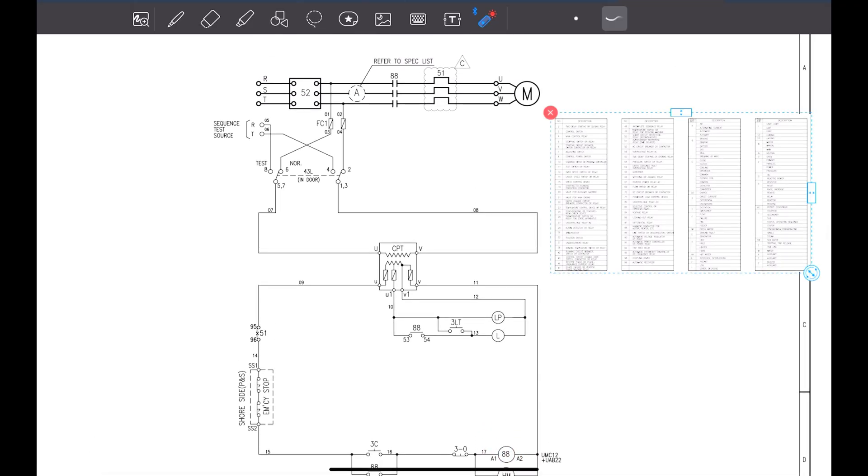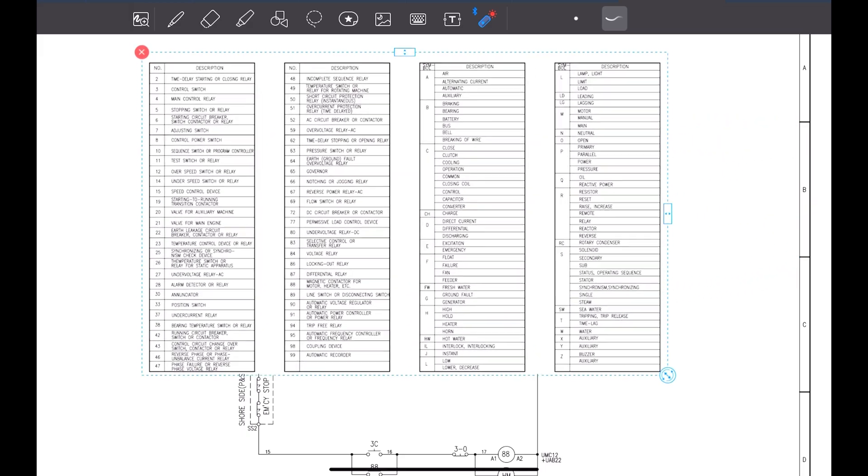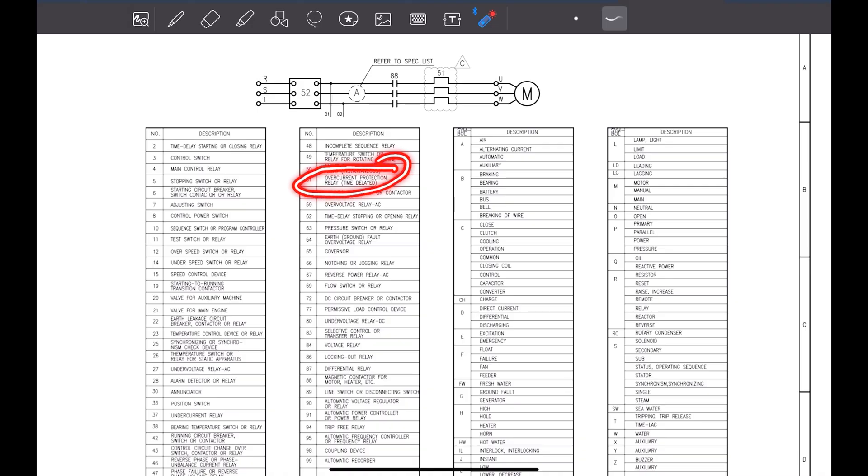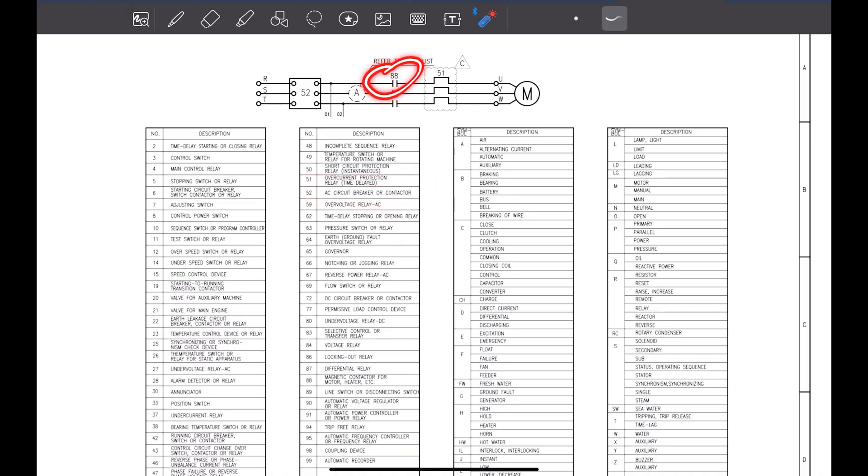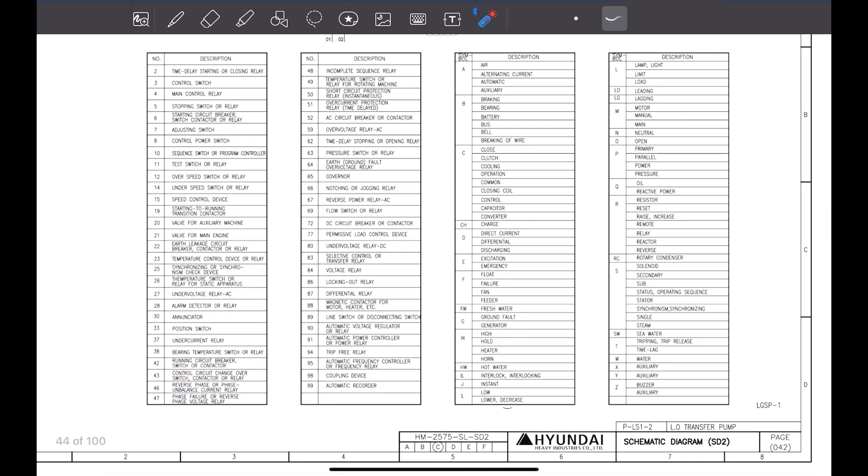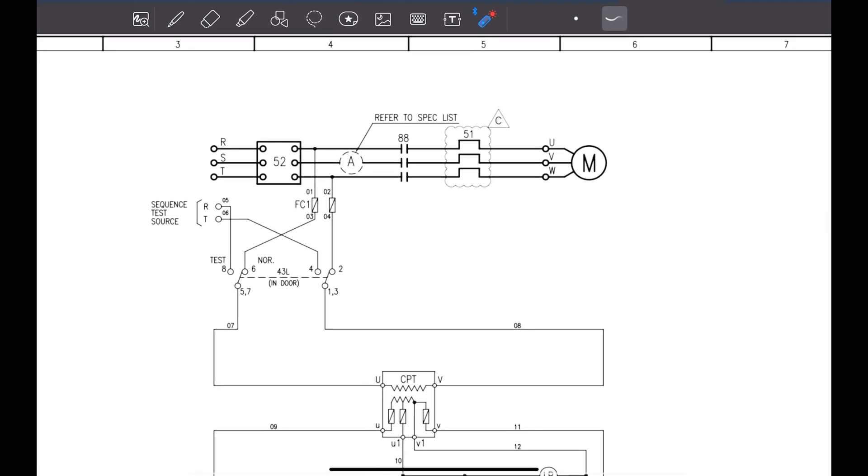You might be confused if you are a beginner what does this number indicate. That is why I told you in the beginning, see, all the manuals have information how to read the manual. As you can see in this page, see the number 51, what does this number 51 indicate. 51 is overcurrent relay. Number 52, what does this mean. 52 is the main circuit breaker. The 88, 88 is the magnetic contactor. 43 which I told you. 43 is selector switch.